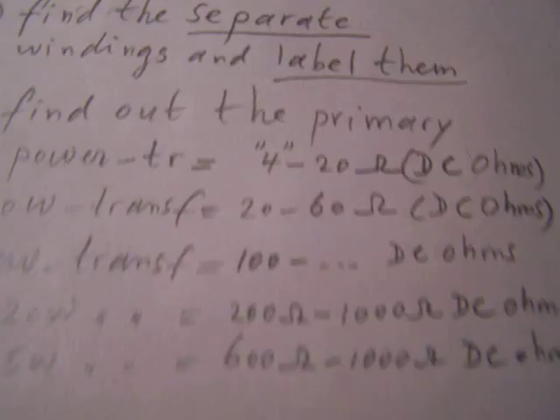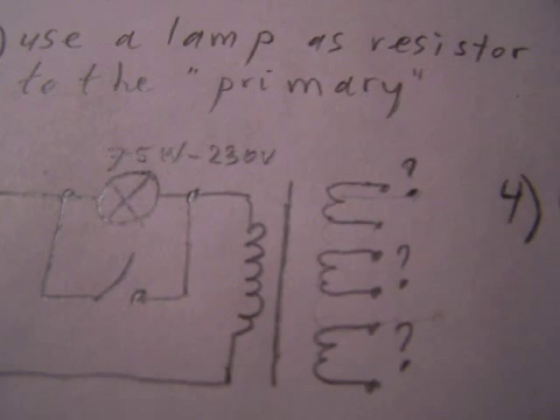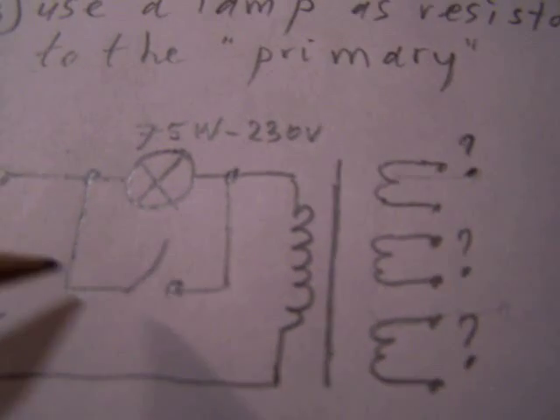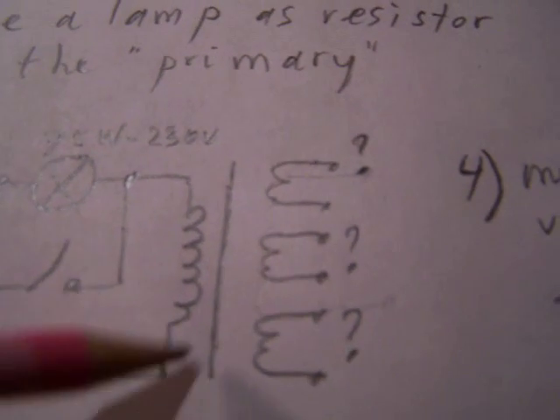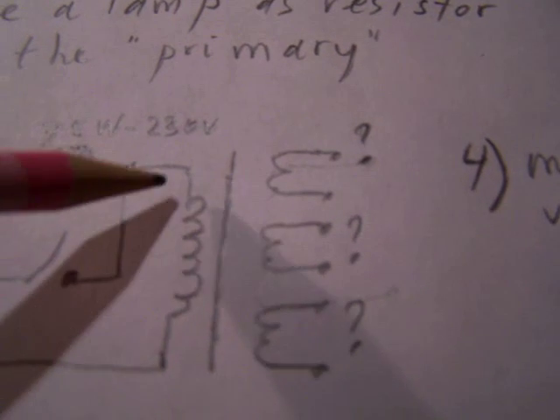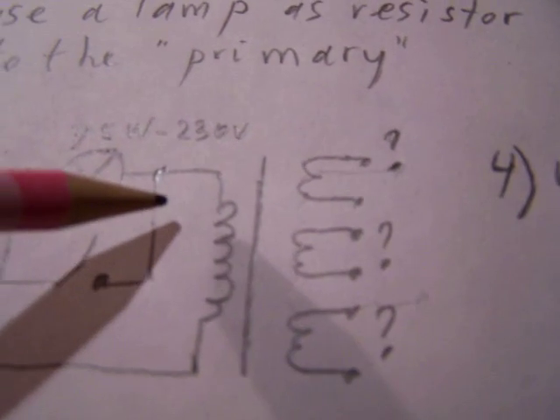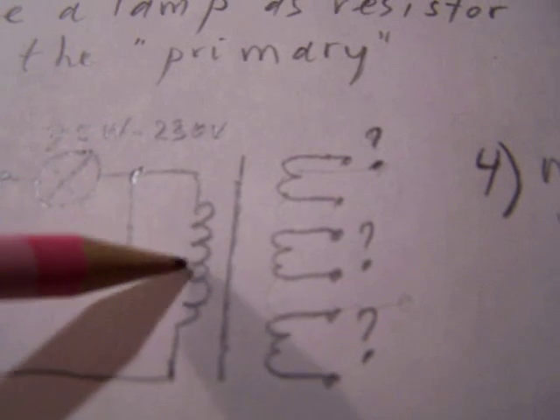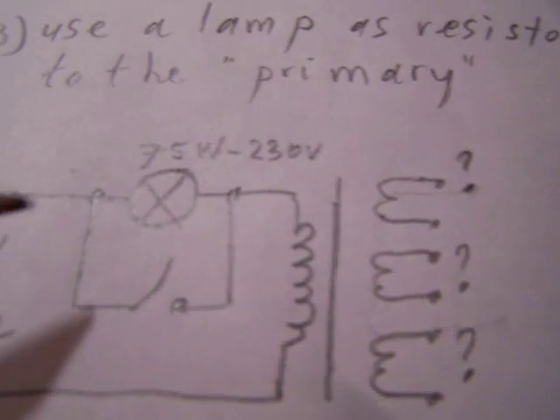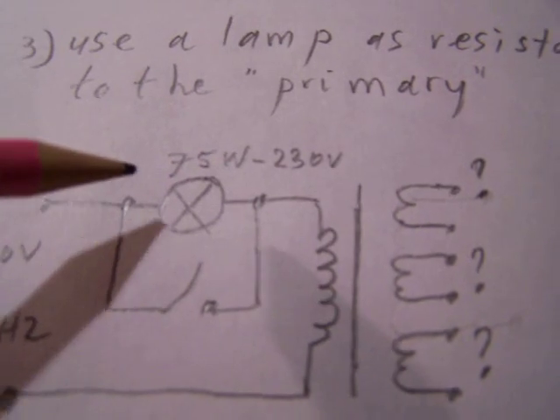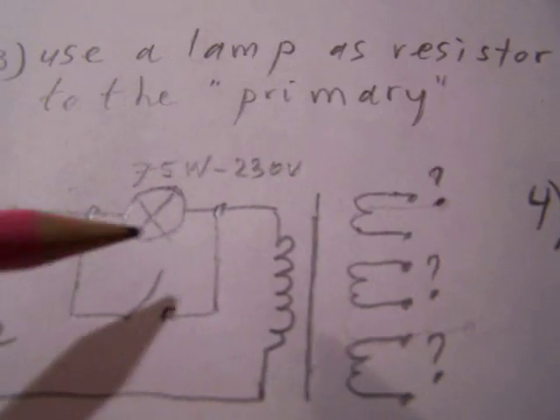And the most important thing here is that at a certain moment we use a lamp. Even when you make mistakes in the connections on the primary of the transformer, and mistakes in the phase of all these windings you have connected together, there's no problem, because this lamp, 75 watts, safeguards your transformer.